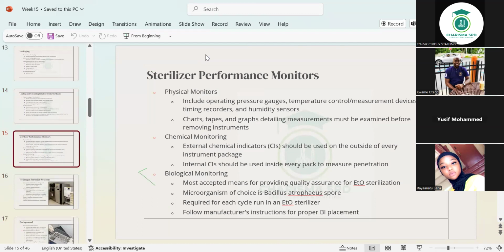Sterilizer performance monitors. There are physical monitors, chemical monitoring, and biological monitoring too. The physical monitors include operating pressure gauges, which I told you about in the steam section. I showed you an image of a sterilizer with the dashboard, the digital screen, where you see the temperature. This one too, you're going to see the temperature, because remember, even if it's cold, there's supposed to be a temperature limit. But this one is not even cold. It's just low temperature, but not cold.